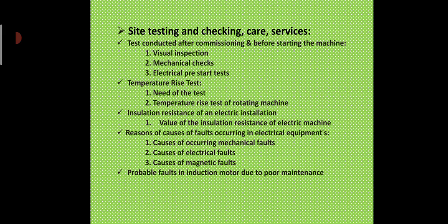Now we shall study the reasons for mechanical and electrical faults. Causes of mechanical faults. First is the causes of improper bearing. It may be long use of the bearing, defective fitting of the bearing during maintenance, improper lubrication, using the wrong grade of grease, or feeding less quality of grease.